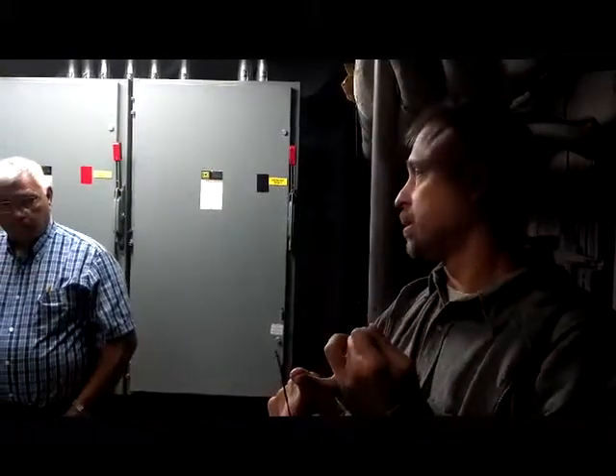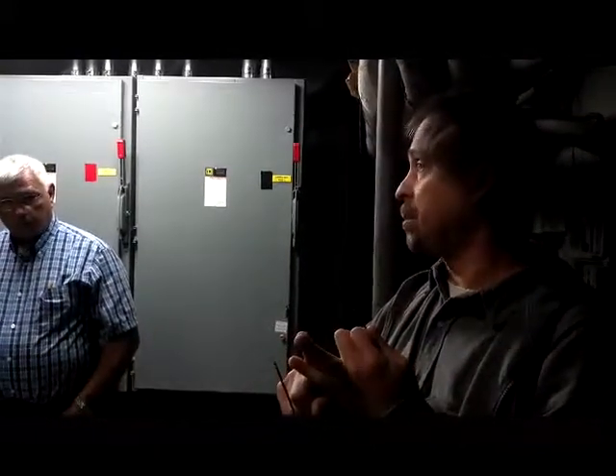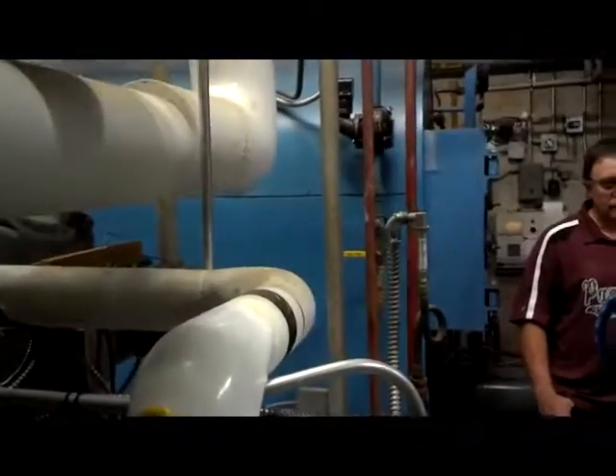As an example, 4 pounds of steam equals 224 degrees. 8 pounds of steam is 234 degrees, which is more pressure and more temperature. Although an electric is a little different, on a fuel-fired boiler, it's less efficient to push 8 pounds versus 4 pounds. Okay, you're talking about the big boiler, the big blue Kewanee. Yeah.